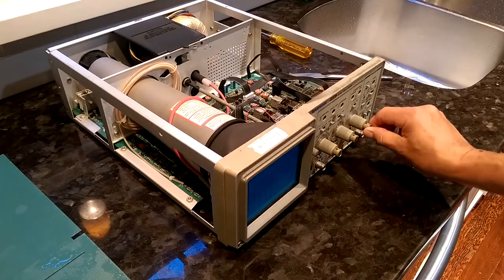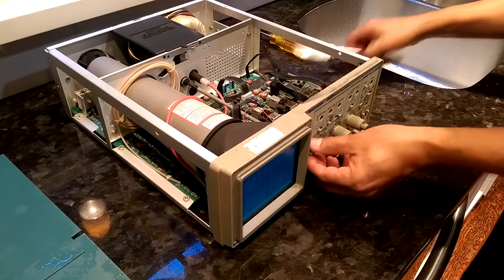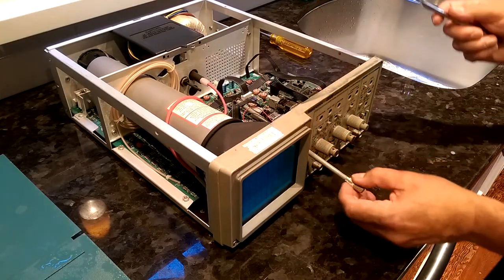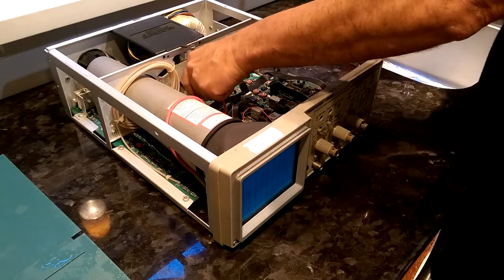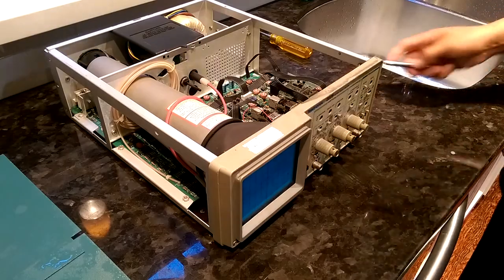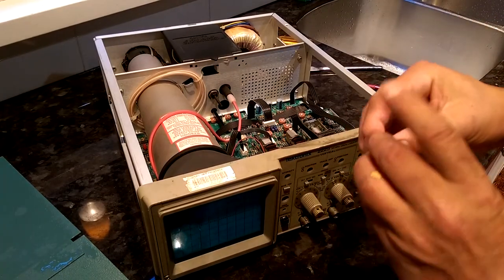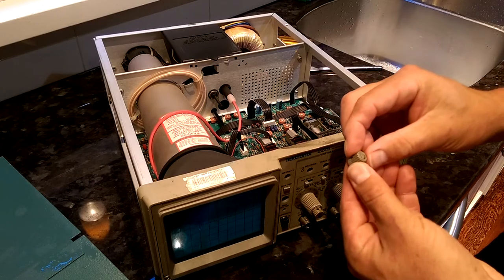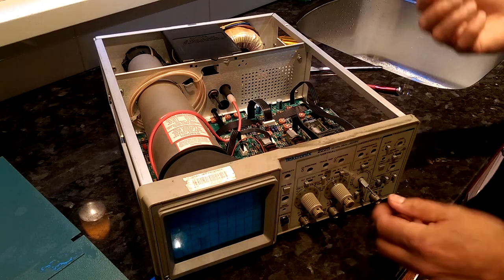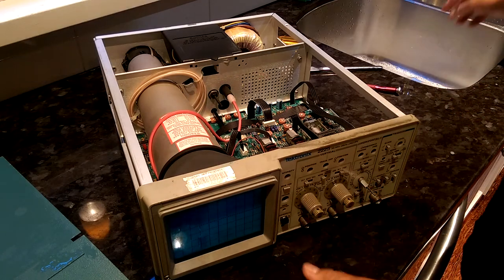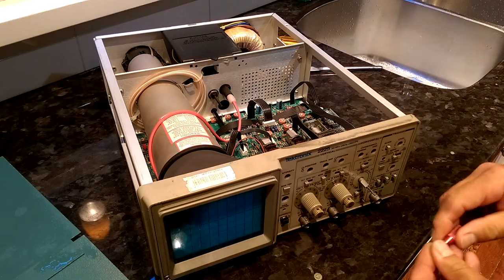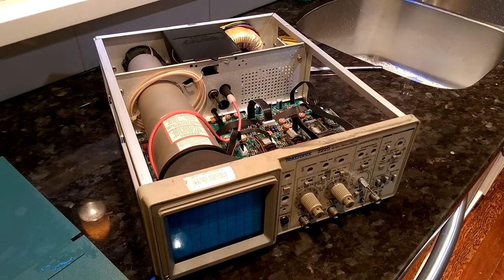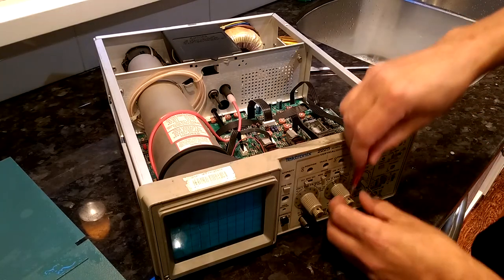Those have set screws, so I'll have to use a little more smarts with that. The focus knob is back here. Okay, so just need to loosen the set screw and then this just pops off and it's indexed. This one isn't. And I don't want to lose the set screw, so I'm going to pull that out before I throw that into the soapy water.